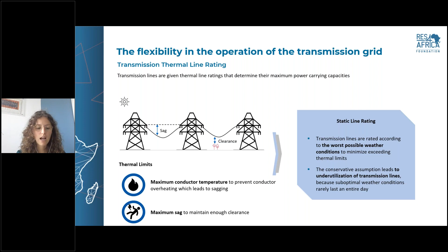So during operation, what is being done already in Belgium, in France, and more system operators are implementing, is the dynamic line rating. So let's measure in real time which are the real conditions on the line. Is there wind? Because wind is cooling the line, so the temperature may be lower than expected, than the worst condition. Is it night? Is the air temperature very low? In all these conditions, probably I can make flow on the line a current that is higher than the static rating capacity.